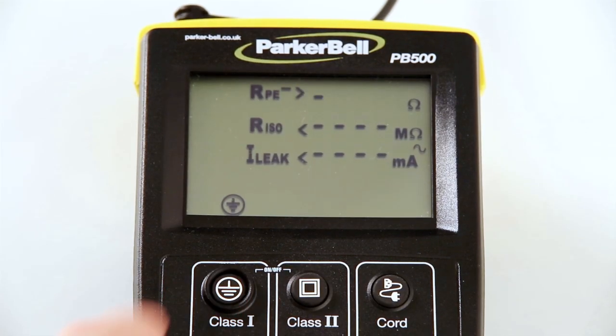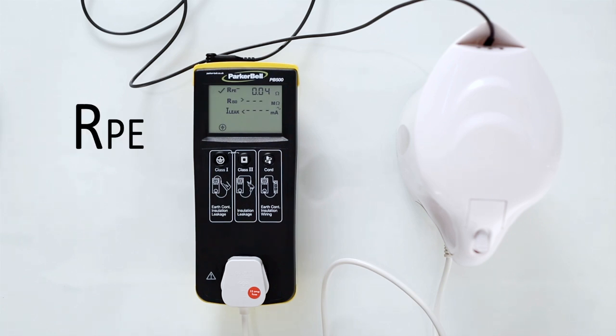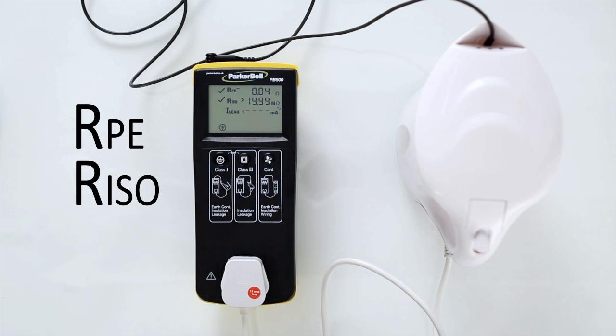Press the Class 1 button and the PB500 will automatically perform the earth continuity RPE test, the insulation RISO test, and the leakage ILEAK test.